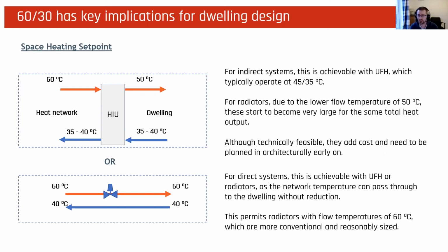But for radiators, and a lot of developers have done radiators for a long time, that's what they're comfortable with. 50 degrees is a lot lower distribution temperature than typical. You know, we've moved from 80 degrees down to 70 degrees, and in some cases we've started to move to 60, but 50 degrees is a step even further. And these radiators start to become quite large.